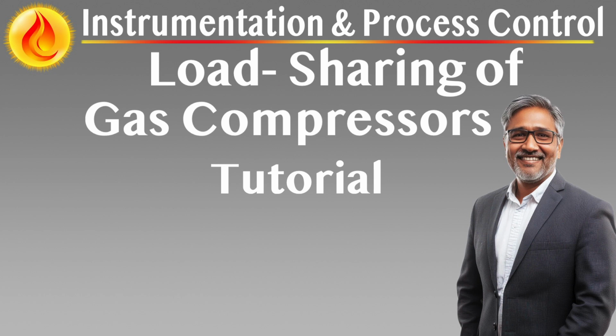Primary capacity control, unified flow or pressure regulation across parallel compressor trains. Overview. Primary capacity control forms the cornerstone of throughput management in parallel compressor operations. It ensures that the total flow or discharge pressure of the compressor network is tightly regulated against process demand while coordinating with both load sharing and anti-surge protection loops. This layered approach not only optimizes compressor output, but also guarantees that surge margins are never compromised, regardless of changing process dynamics.